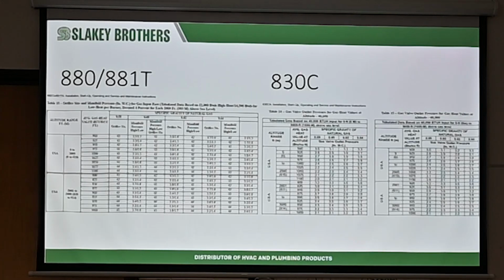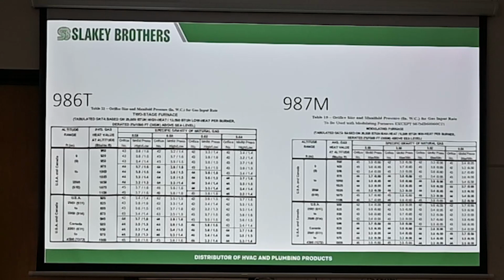We're not going to go over the 830C because we're not in this area. But the numbers for the 880s are pretty much about the same. Here's your 0.6. You can see your 1.6, 1.4 for fire rate on the low, and still 3.3 to 3.6 on the high. So again, if you always stick to that 3.5, 1.5 on a 2-stage, you're probably going to be okay. I've done that for 17 years, never bit me in the ass. The modulating furnace will, though, if you don't set that up.